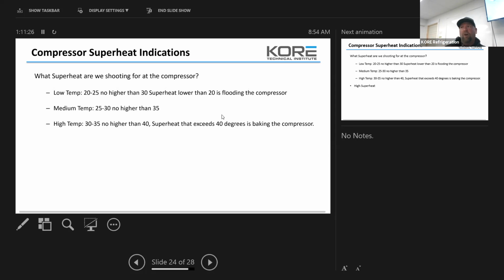So anytime you guys are charging or checking superheat, don't finish until that valve's at optimal condition, especially on smaller systems. A lot of systems get overcharged because we keep dumping, thinking it's empty because the sight glass keeps flashing. The sight glass is flashing because that valve is wide open. As that valve throttles back, it starts to hold back more liquid refrigerant, and then the sight glass clears. So let's make sure that when we're charging or dialing in superheats and topping off charges, we check those charges when we're close to optimal running conditions, within 5 degrees. Okay, does that make sense?